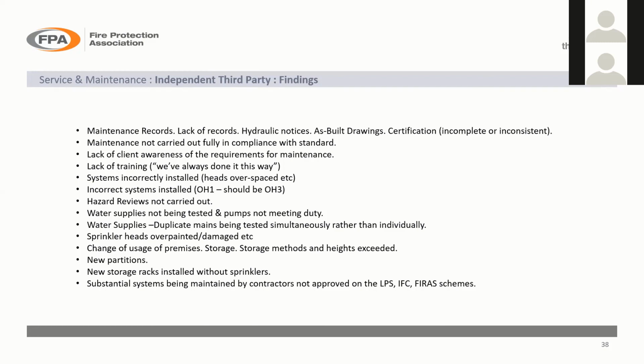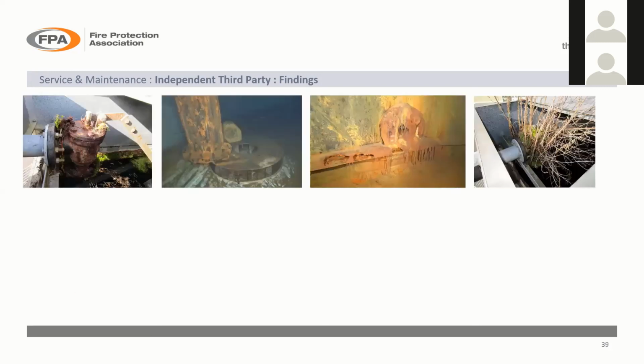And finally, we've been to systems where the maintenance contractors haven't got much in the way of any kind of accreditation to carry out maintenance on sprinkler systems. They're more likely to be alarm companies who convince the user that they can do the servicing on the sprinkler system as well. The LPS schemes, for certain, and maybe the IFC and FIRAS schemes, all have their own maintenance requirements of companies. As a user, you'd be well advised to look into that and make sure that the people coming to service your system have the competency and can provide the certificates of training showing they can work on these systems. It's very important. It's too late when your system's a pile of scrap on the floor because you've had a fire. Take action now, and that's my final slide.